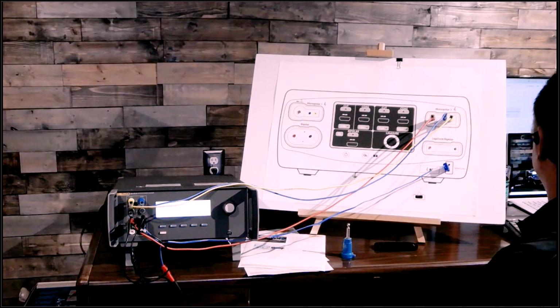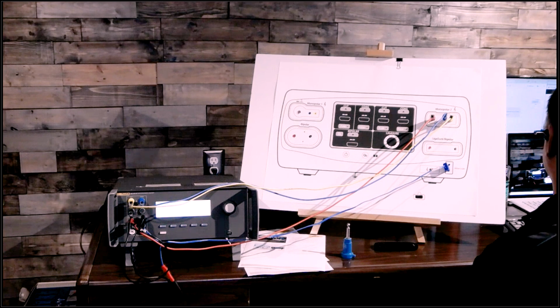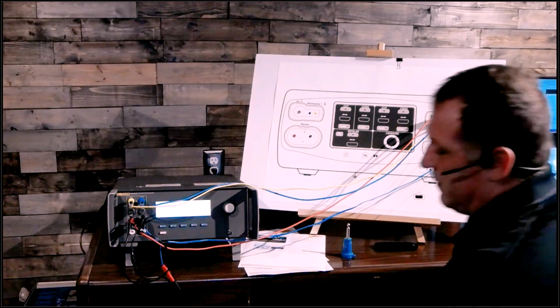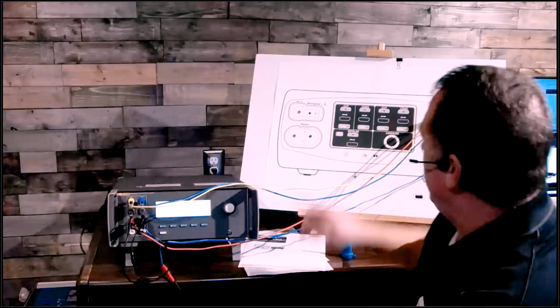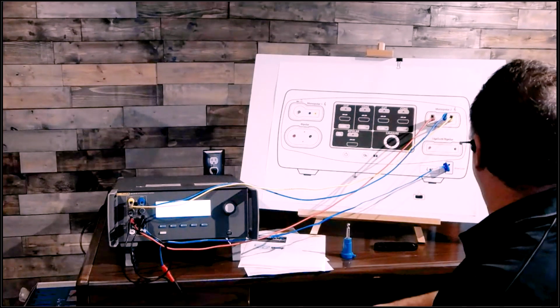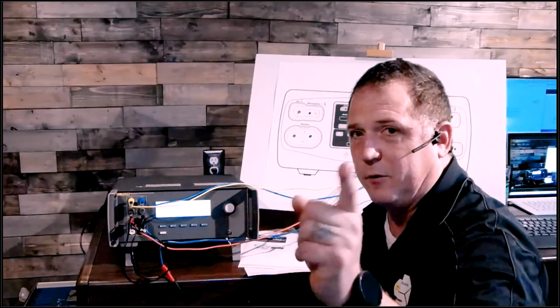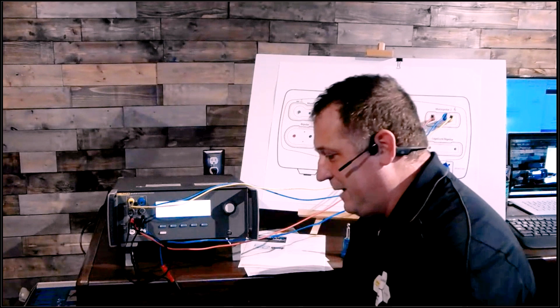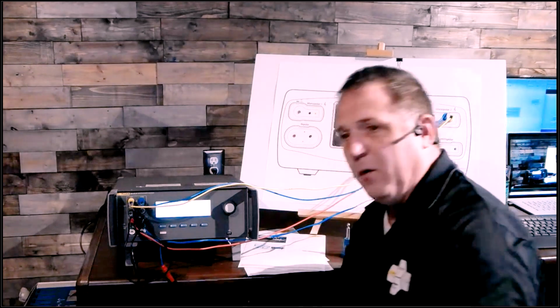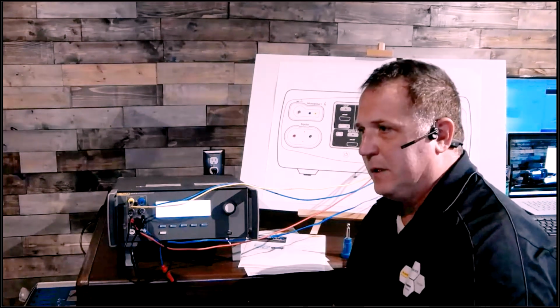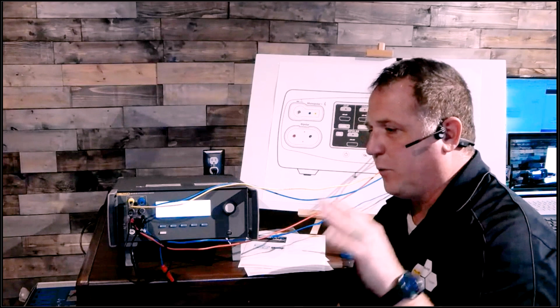One more question, Justin. Is it necessary to go to service mode with the device under test? I just turned on this ESU, my paper ESU, two times without going into service mode. So no, you don't have to, especially if I want to test how it's working in the field.